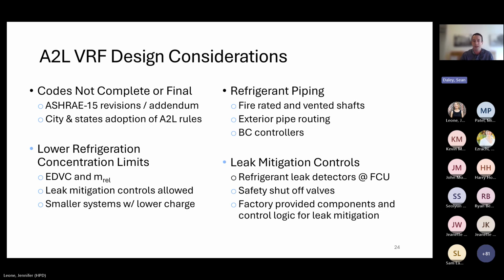So, refrigerant piping. We got into it a little on Kevin's slide before with the fire-rated shafts and ventilated shafts. Again, there are some discussions about ASHRAE 15 making that a little more lenient, but nothing has been finalized yet. So as of right now, we need fire-rated shafts when we have a substantial run of vertical piping within the building, and those shafts need to be ventilated. Kevin touched on this as a possible solution as well. Moving forward, you're probably going to see a lot more exterior refrigerant pipe routing, especially on retrofit projects where you don't have space for the fire-rated shafts. That's something you're going to see to comply with the code.